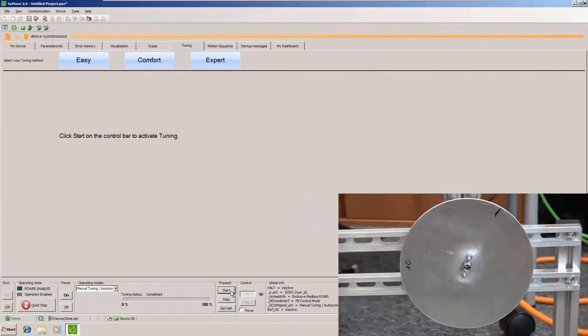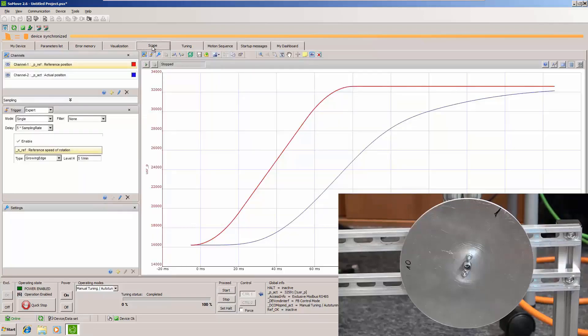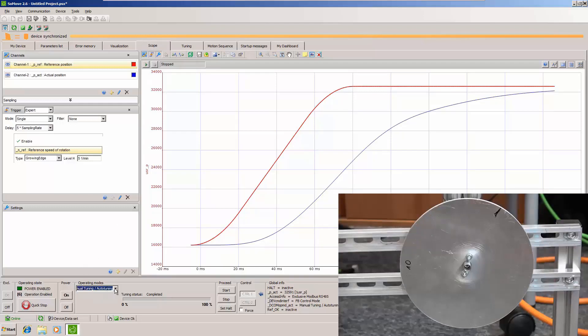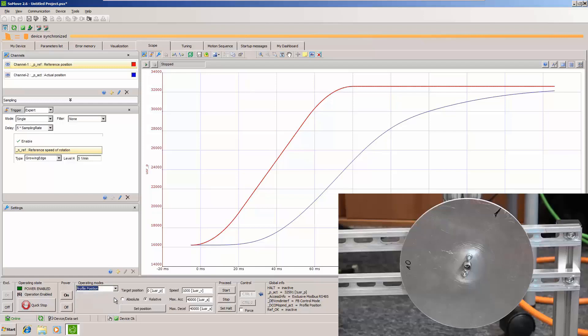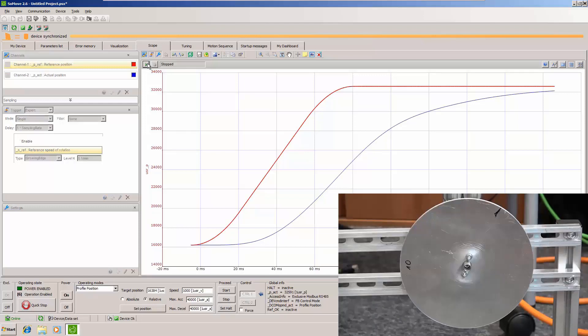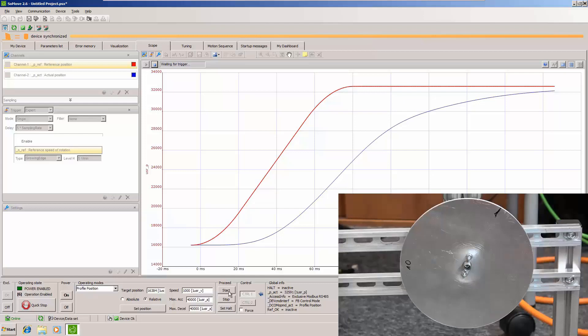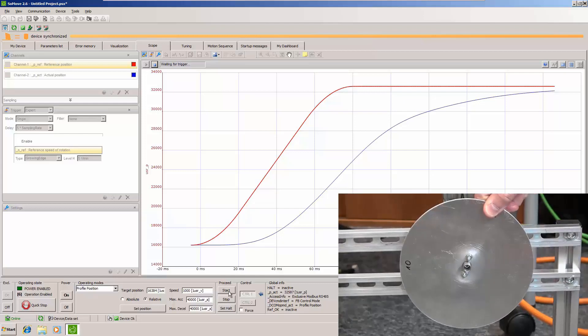And now let's do some tests. We will do a scope. Now let's see. Profile position. Again we will do one rotation with the same parameters. Let's run our drive. And here you can see that the control loop is much stiffer. I cannot move it.